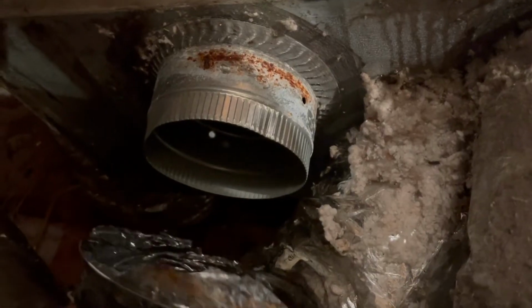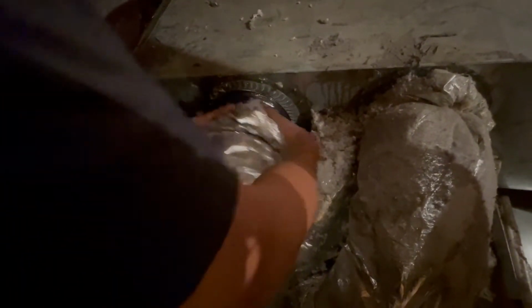It's very wet, and that is from, look here, good old water. So you don't want your ducts touching. You want your ducts in a row, and you don't want them touching, and obviously you want to seal them, because this is not being sealed. Wow, that's insane. Yeah, boy.